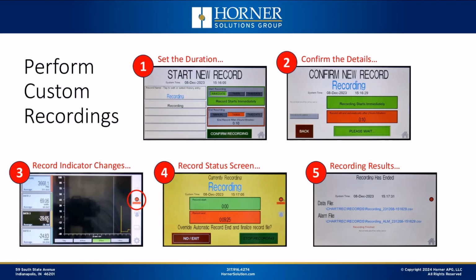And while the test is running, there in step 3, there on the screen, I've kind of circled the record indicator that will be changing its appearance so that it's obvious that there's a recording going on. And then, during the recording process, if you want to see what the status of things happens to be, you can press that record button and it will take you to a record status screen telling you how long is left in the recording process and that sort of thing. And then at the end, the unit will effectively tell you the file location on the memory card where you can find the electronic results for the test that you just ran.